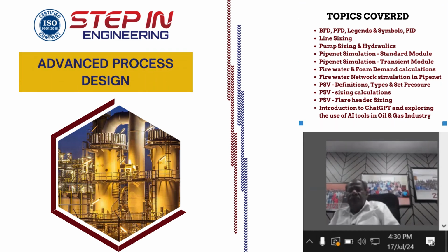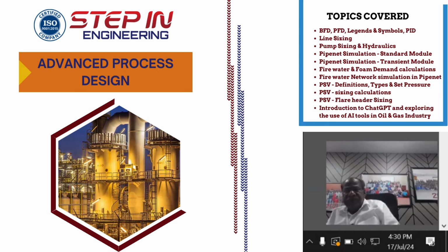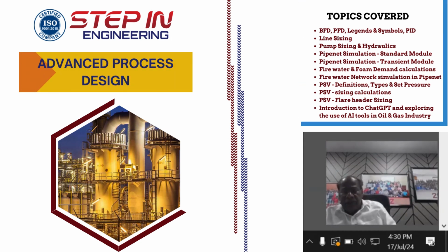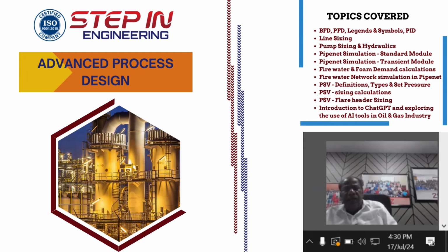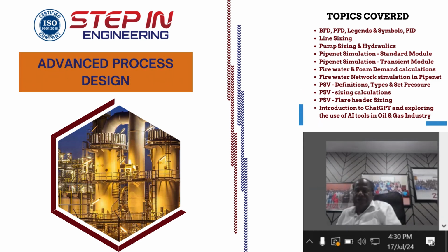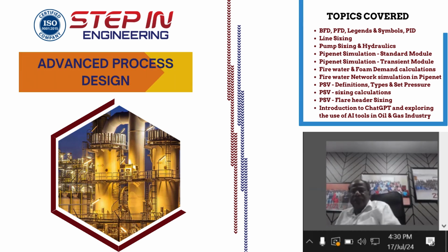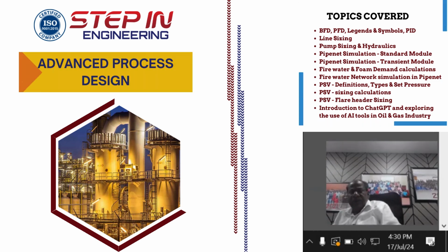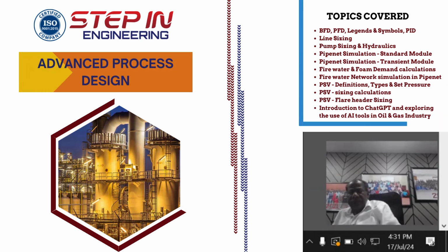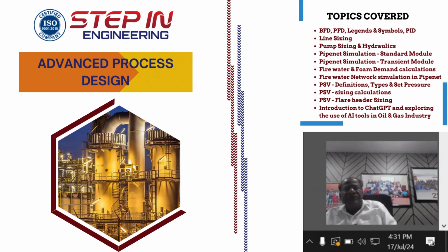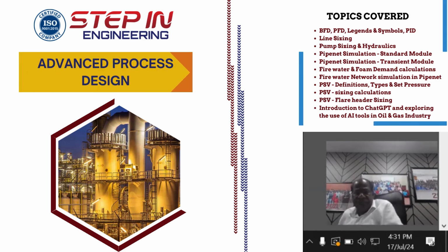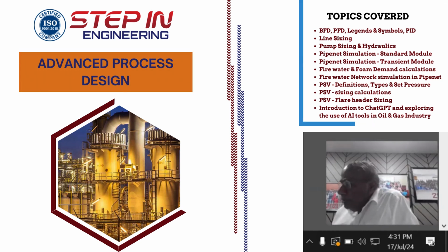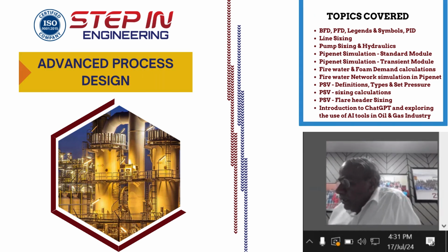A pilot operated PSV is almost 10 times the cost of a conventional pressure relief valve. I cannot just blindly put in a pilot operated relief valve and say that my system is safe. No, that is not the way. The design should be fit for purpose. Where only a conventional relief valve is required, I cannot go for a pilot operated relief valve. These are the things that will be discussed and demonstrated in modules number 8, 9, and 10.